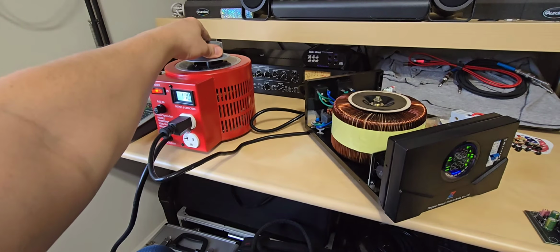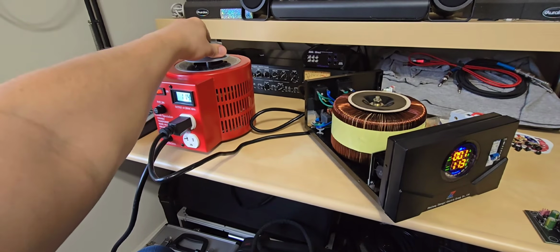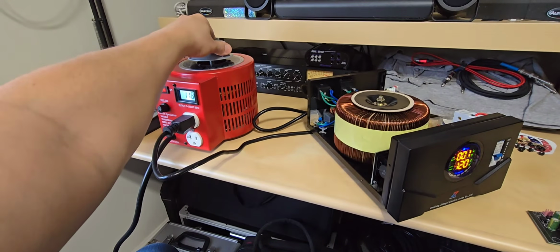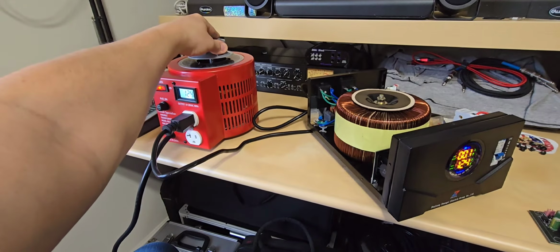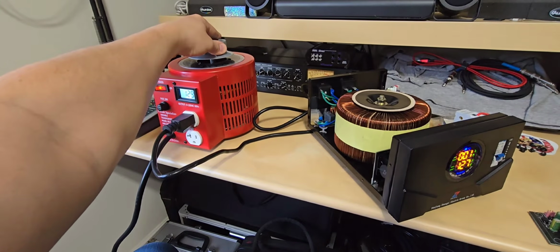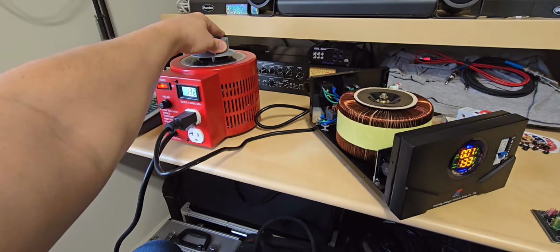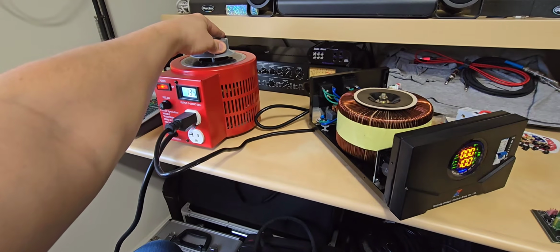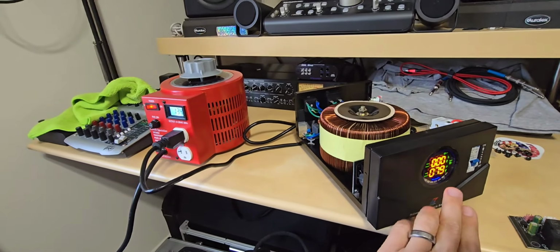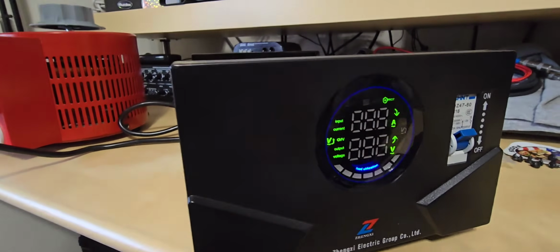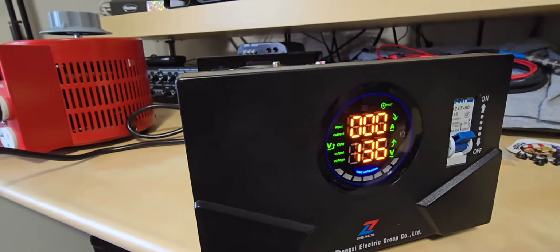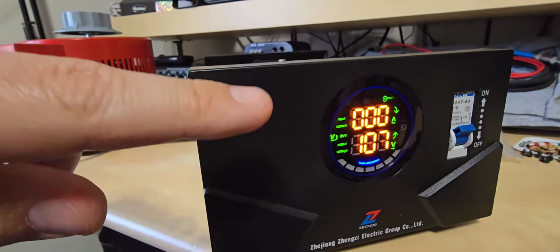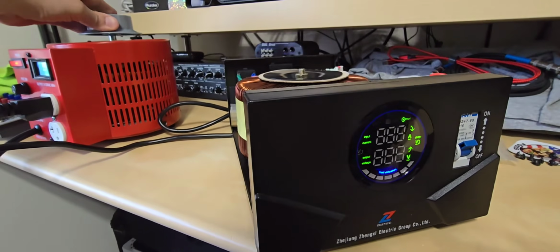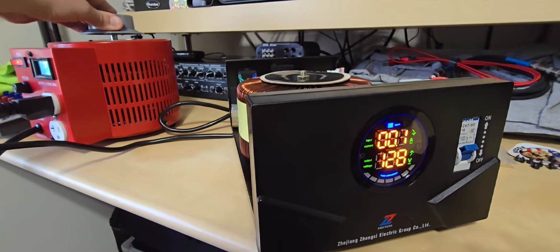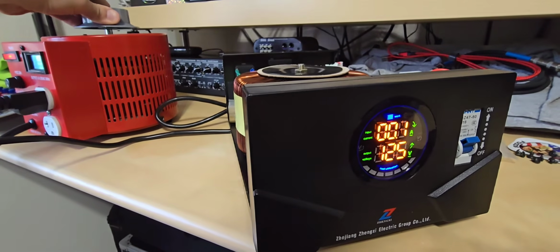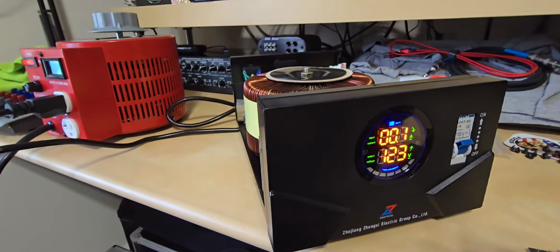Now we'll bring this back up, and it will not re-engage until the voltage is back into a safe range. And finally, on the overvoltage protection, once this hits 132, it should shut down too. And there you go. Now, it's going to blink like that. You're going to see that it is going to continue to blink. You'll see the protect continue. But then once the voltage gets back into a safe range, the microcontroller should re-engage the relay to the output outlets in the back.